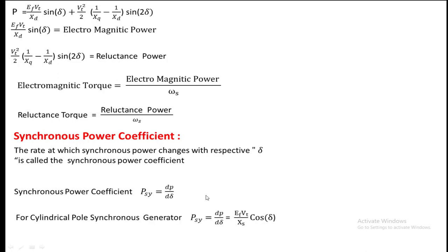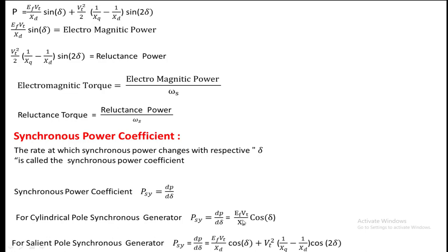Differentiating with respect to delta, for a cylindrical rotor the synchronous power coefficient is EF·VT / Xs · cos(delta). For a salient pole generator it is EF·VT / Xd · cos(delta) + VT²·(1/Xq − 1/Xd)·cos(2·delta). A high synchronous power coefficient means the stator flux and rotor flux are strongly coupled — it won't be affected even if there is some electrical load on the stator or a change in supply voltage corresponding to EF·VT. For the salient pole generator, the synchronous power coefficient also depends on Xd and Xq as well as the excitation.